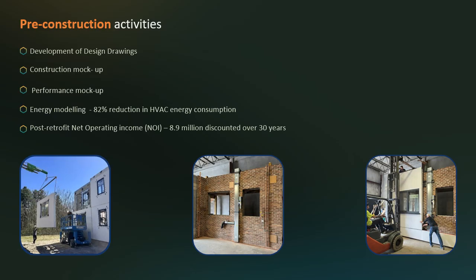An energy model has been run. We are saving about 82% in terms of HVAC energy consumption, which is quite drastic, especially given that we're adding ventilation to each of these apartments. There's no ventilation right now. So they're all going to get ventilation and cooling, which they didn't have before. But we're also reducing energy consumption by 80% because we're not pumping heat all the time, and we don't have the leaky envelope that the building currently suffers from.